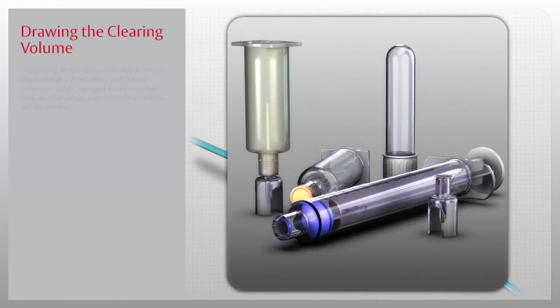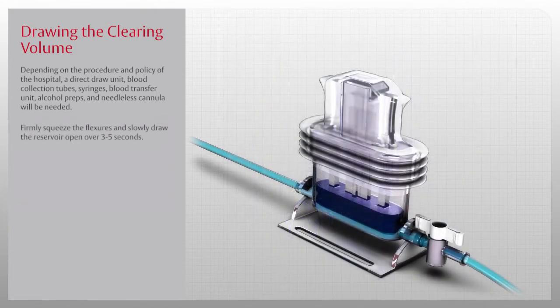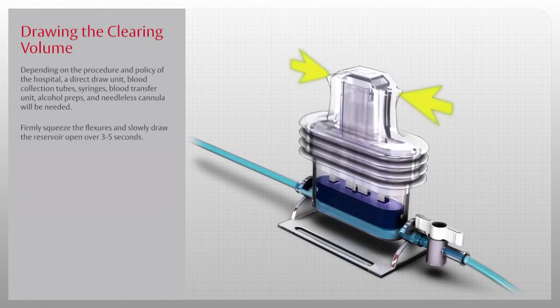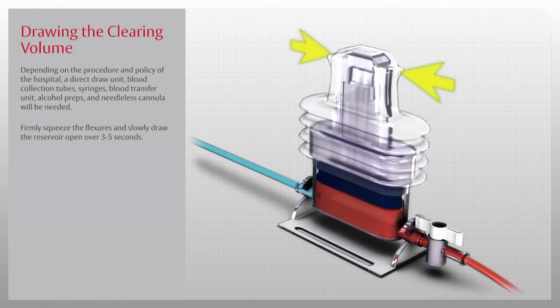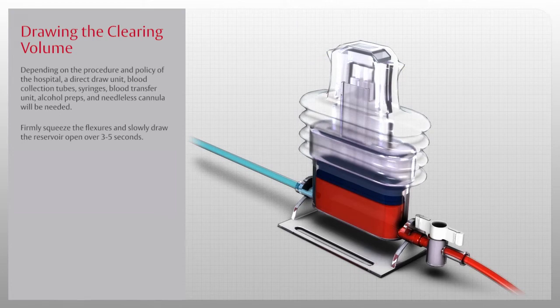Note: depending on the procedure and policy of the hospital, a direct draw unit, blood collection tubes, syringes, blood transfer unit, alcohol preps, and needleless cannula will be needed. First, firmly squeeze the flexures and slowly draw the reservoir open over 3 to 5 seconds. Then, close the shutoff valve by turning the handle perpendicular to the tubing. This is to prevent aspiration of blood from the reservoir.